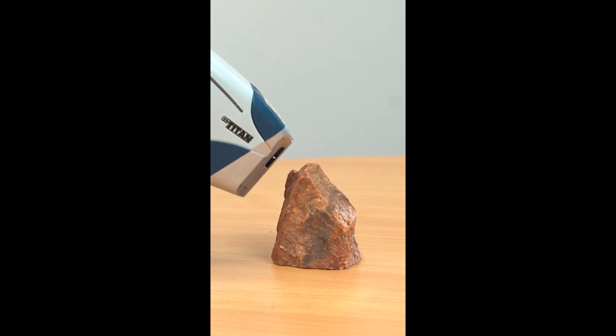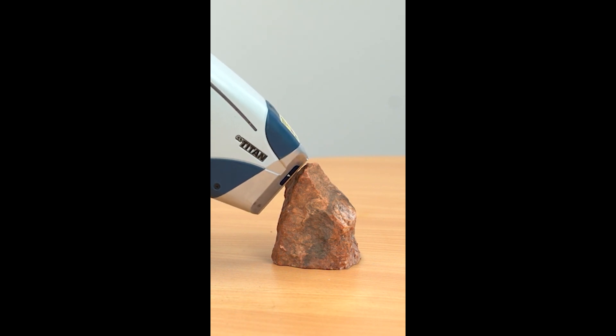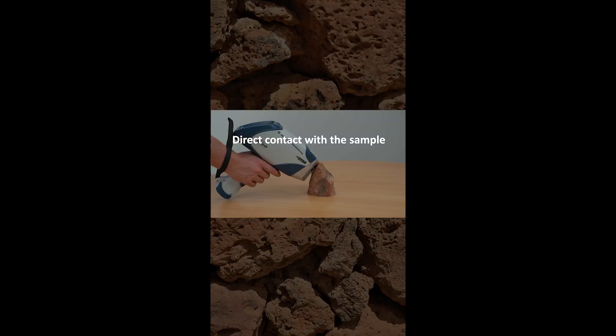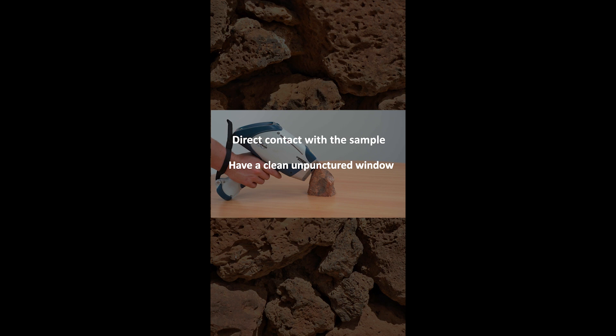So the key thing for taking good analysis is to have direct contact with the sample, having a clean, unpunctured window on the instrument, and analyzing for the full recommended time.